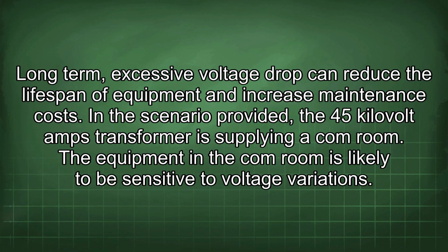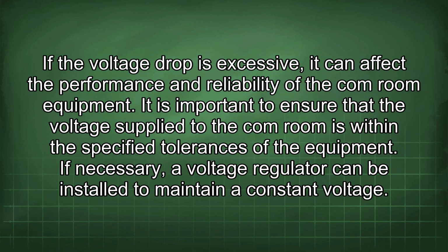Long-term, excessive voltage drop can reduce the lifespan of equipment and increase maintenance costs. In a scenario provided, the 45 kVA transformer is supplying a COM room. The equipment in the COM room is likely to be sensitive to voltage variations. If the voltage drop is excessive, it could affect the performance and reliability of the COM room equipment. It is important to ensure that the voltage supplied to the COM room is within the specified tolerances of the equipment. If necessary, a voltage regulator can be installed to maintain a constant voltage.